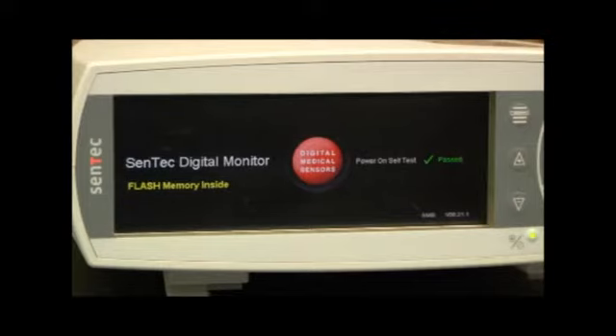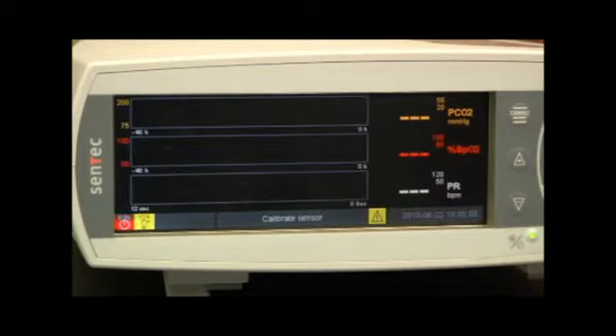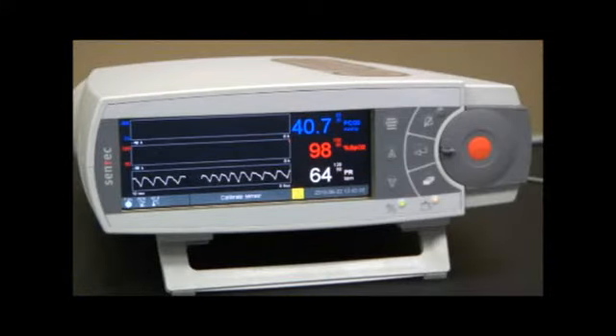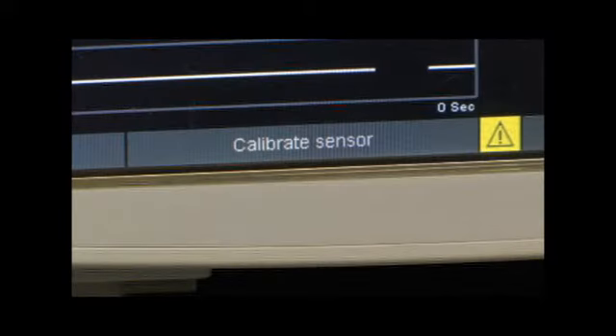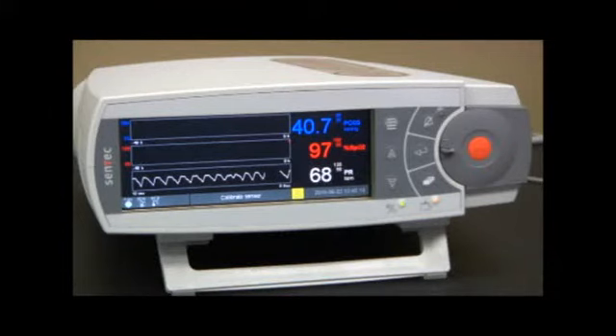This initial calibration should take between 3 to 5 minutes and will be adequate for the first 4 hours of monitoring unless prompted by the monitor. Once monitoring time has reached the initial 4-hour interval, the monitor will display Calibrate Sensor in the status bar window. As soon as the monitor prompts the message, Calibrate Sensor, remove the sensor from the patient. Depending on which interface you are using, this can be accomplished in the following manner.